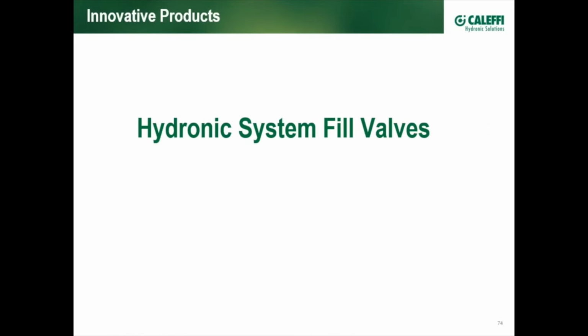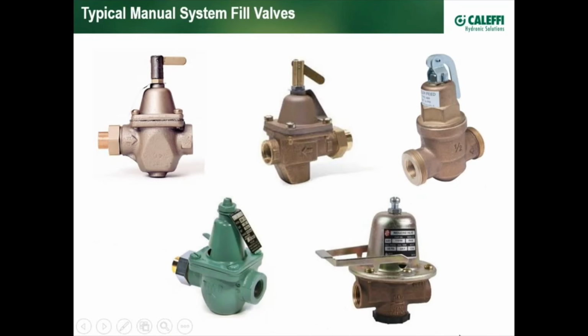Moving on, hydronic system fill valves. Many on the market, all great brands. These all have in common one thing, a lever or handle that gets flipped over before the system is filled. That disables the pressure reducing qualities of the valve and allows the valve to basically pass straight through, and flow is dictated by the internal resistance of the valve itself, as well as the mains pressure and perhaps the back pressure of the system. The system starts to get filled up, and hopefully before the pressure relief valve on the system is exceeded, spilling water all over the floor, someone comes down, flips the valve back over into pressure reducing mode to finish the filling process.